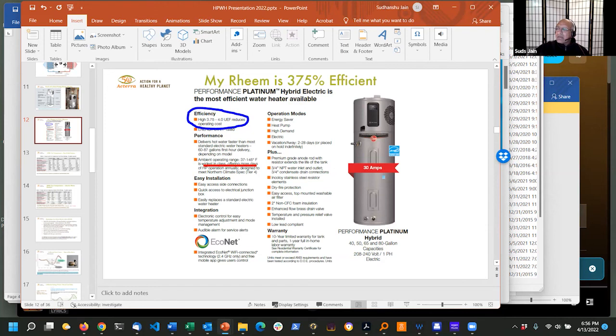What about a water heater in a crawl space? I think a crawl space would be an ideal place for a heat pump water heater. The only thing is you'd need to be able to access it to replace the filter once a year, and since there might be more dust in a crawl space, you might need to replace it more often. I don't even replace mine, I just rinse it off once a year.